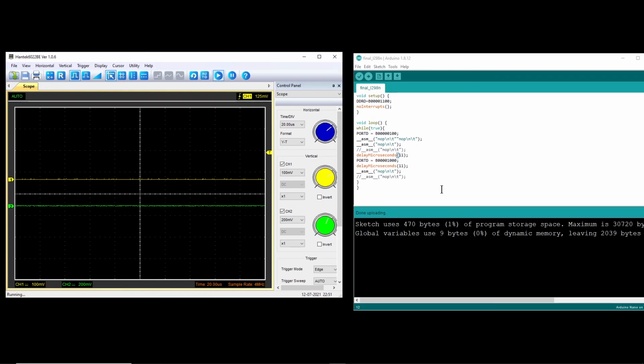However, at the output of the H-bridge, sometimes the positive polarity will be connected to the probe, and sometimes the positive polarity will be connected to the ground of the probe. In that case, you actually create a short circuit through your system, a current of a few amps will flow through your system, and the signal you measure will be completely distorted. So be aware of this error and avoid it.